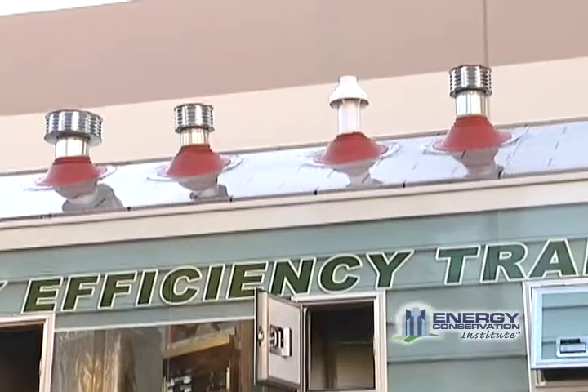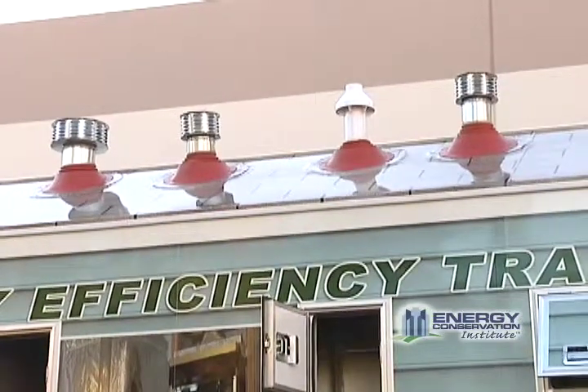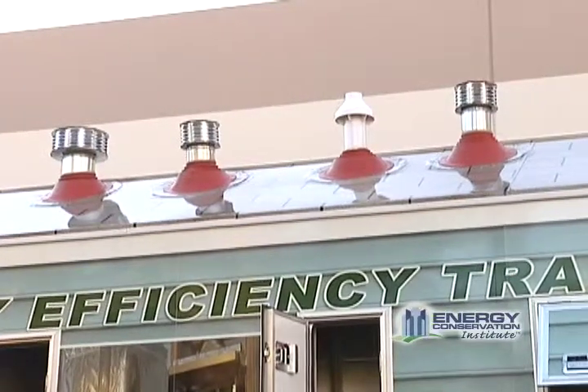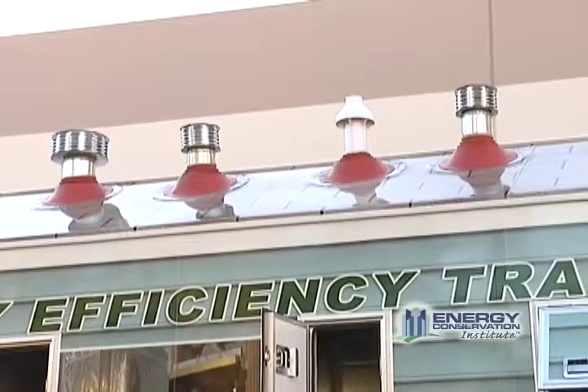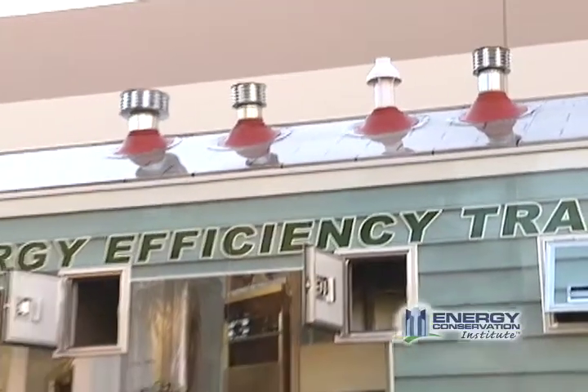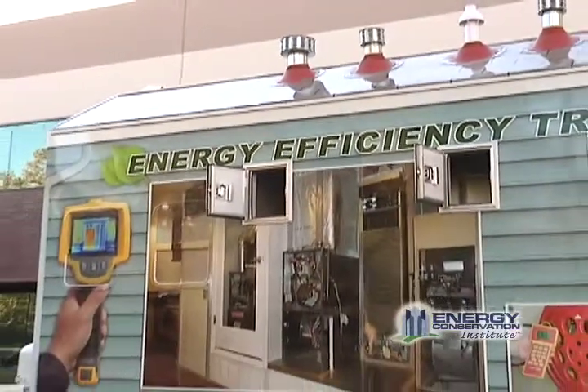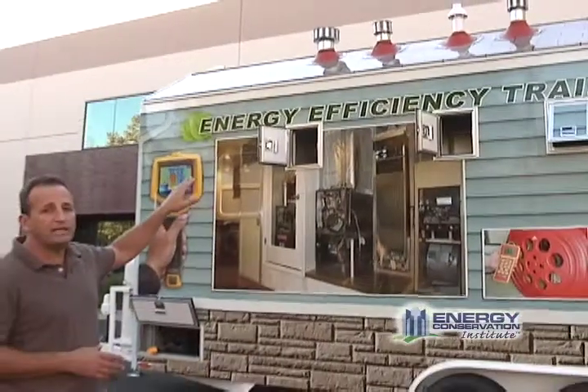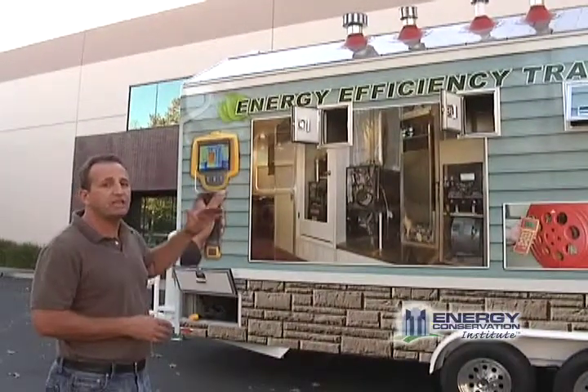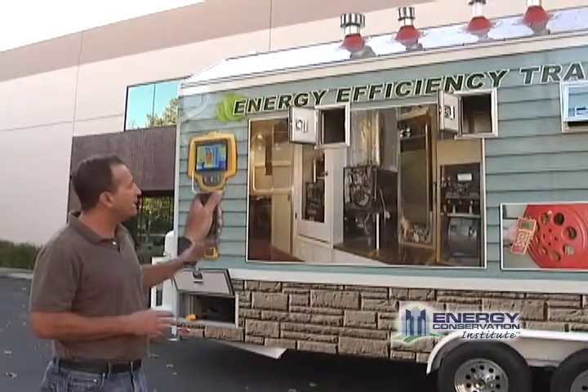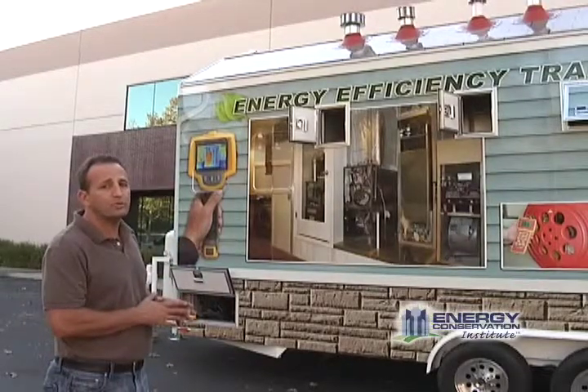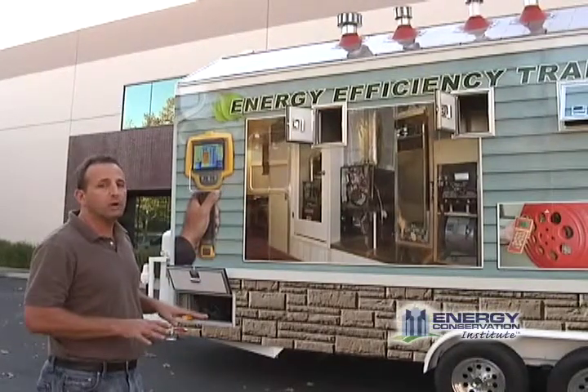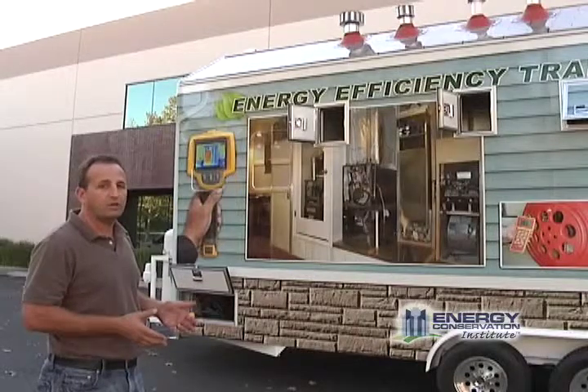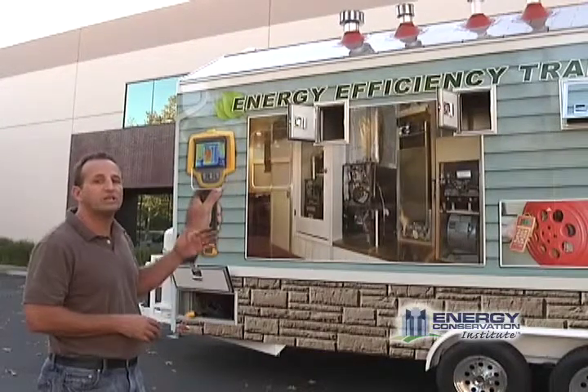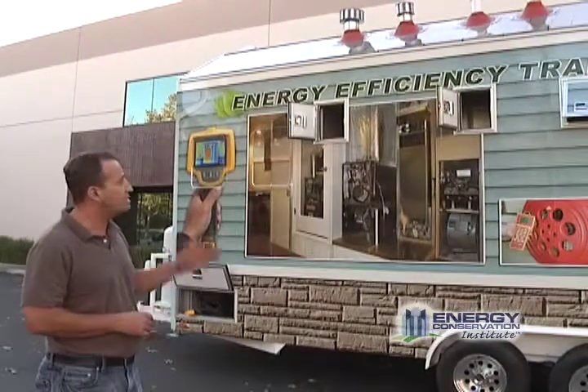If you have conditions where you're not able to achieve proper draft in the furnace, you can go up through the roof ports located in the attic, which I'll point out in a bit, remove the rain cap from the vents, and extend those caps. When we test these labs before they leave, they're all drafting properly, but you may have conditions that warrant extending those vents, and that's how it's done up there.